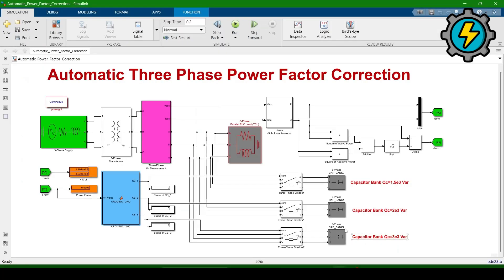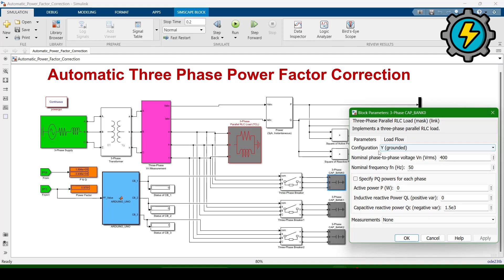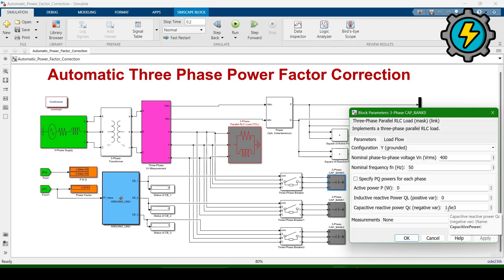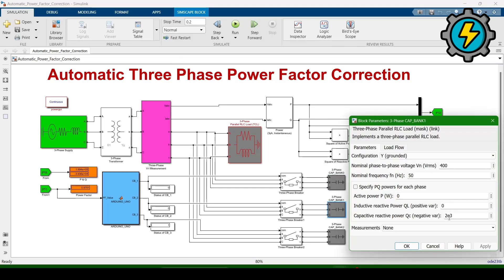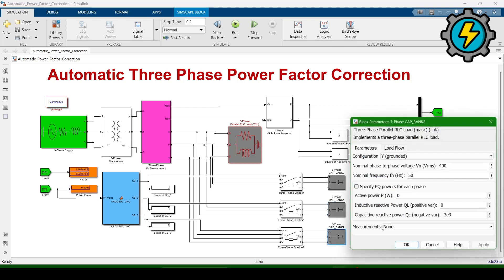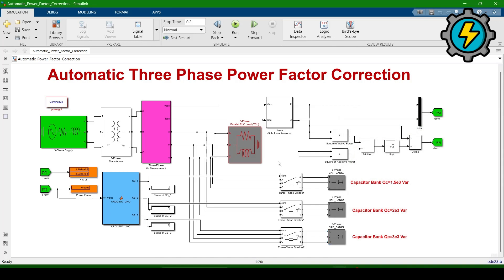Now we will check the capacitor bank values. The first capacitor bank value is 1.5e3, meaning 1500 VAR reactive power. Double clicking shows it is Y-connected (star connected with ground), voltage is 400V, frequency is 50 Hz, and capacitive reactive power is 1500 VAR. The second capacitor bank is 2e3 (2000 VAR), and the third is 3000 VAR.